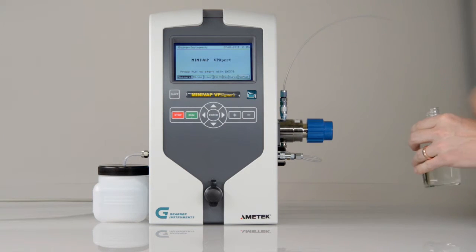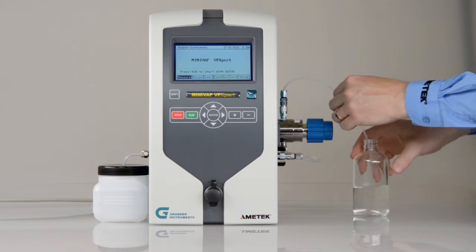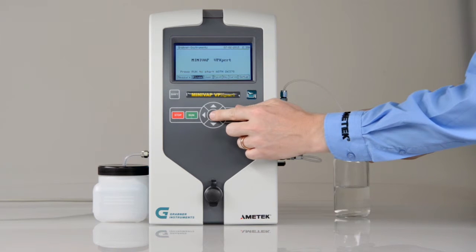Before you turn off the VPXpert at the end of the day, rinse the instrument with a cleaning solution mixed with toluene, acetone and methanol to clean the measuring chamber.